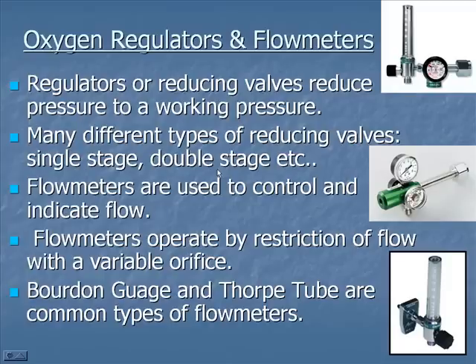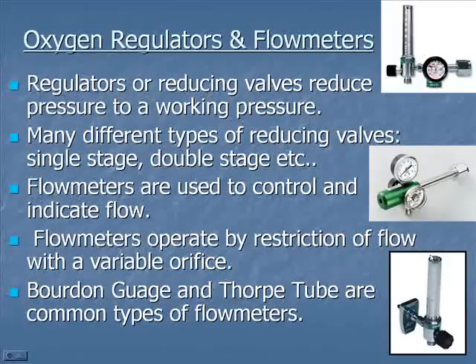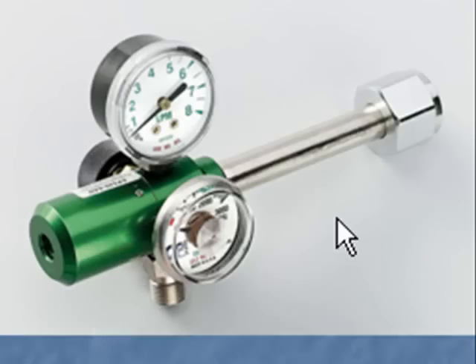There are single stage and double stage reducing valves. The flow meters allow you to set an accurate level of flow to be delivered to the patient. They work primarily by incorporating a restricted or variable orifice. You'll see a little ball that floats up — in particular, in the Thorpe tube, a ball regulates the flow. There's also a Bourdon gauge type where you have a dial to set the needle to a certain setting.